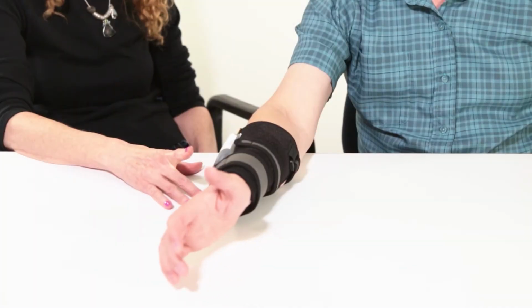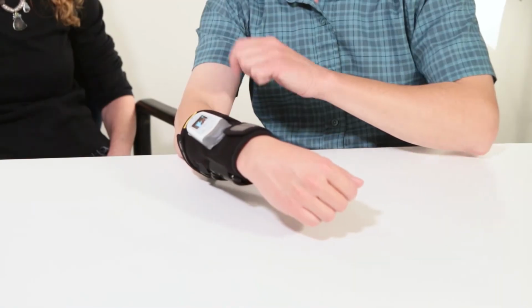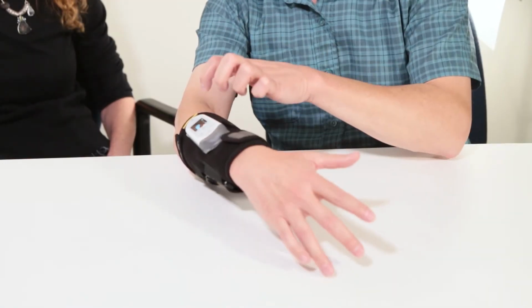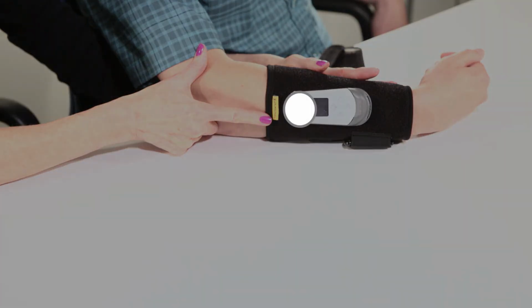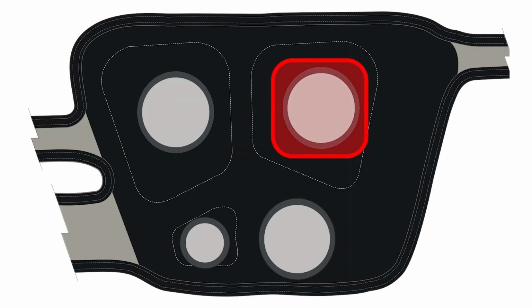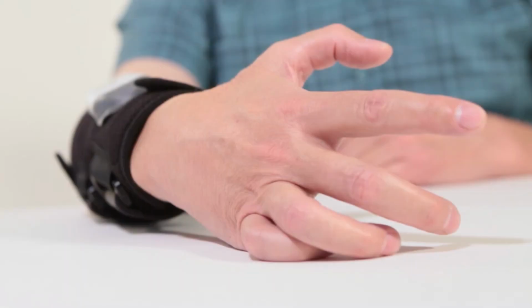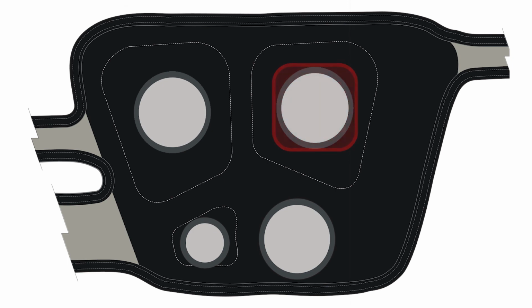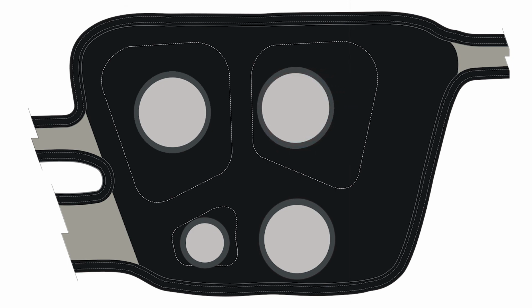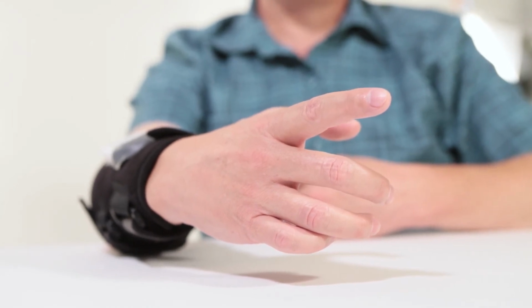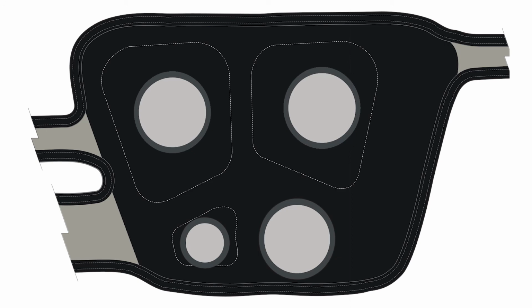With good electrode placement, we'll get good finger and thumb extension, opening, and flexion, closing, like this. The extensor electrode is the electrode that controls the hand opening. It's under the stim and closest to the single strap. If you see more finger extension of the outside fingers, move the extensor electrode inward towards the middle of the garment slightly. If you're seeing more extension of the inside fingers, like this, you'll want to adjust the electrode outward slightly.